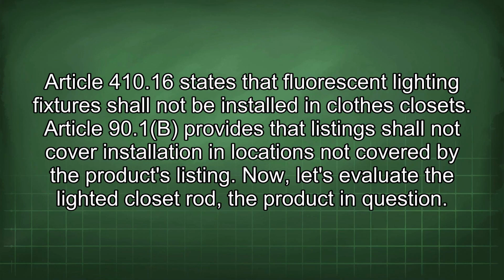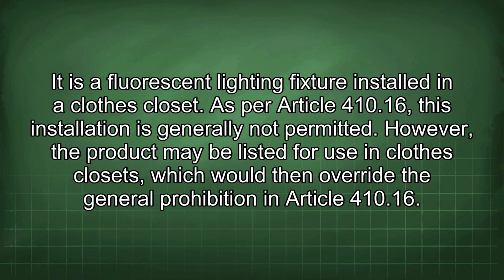Article 410.16 states that fluorescent lighting fixtures shall not be installed in clothes closets. Article 90.1b provides that listings shall not cover installation in locations not covered by the product's listing. Now, let's evaluate the lighted closet rod, the product in question. It is a fluorescent lighting fixture installed in a closed closet. As per Article 410.16, this installation is generally not permitted.